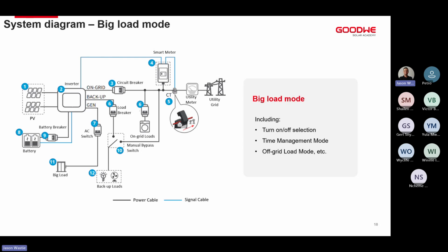So if you're running like a pool pump or a geyser or something like that, you can always have it connected to that port. And if during the middle of the day you've got obviously no Eskom power or no utility power, or you've got utility power, we're running through the backup mode, and we've got all of our loads running, you've got enough PV available, batteries are full, and everything else is available, it will open up the gen port and allow you to start charging or running towards your geyser or anything. During an on-grid application, it will see that as a normal load and be able to run it as normal. It's just during off-grid applications, we can set that time either on or off.